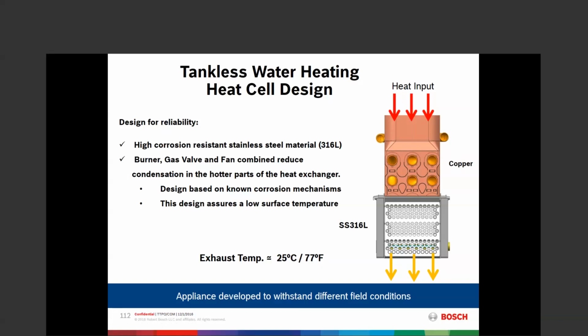And a lot of times some people are looking at that and going, hey, small tubes, that means high pressure drop, but it doesn't. And why it doesn't is these 50 tubes, the aggregate or total cross-sectional area of these 50 tubes has more than 4 times the cross-sectional area of a single pass of the copper tubes. So what actually happens is the water moves through this section, its velocity goes way down. Flow rate, gallons per minute, is going to stay the same, but the velocity goes way down. So in doing that, what we're creating is a huge wetted surface area. So there's a lot of surface area in contact with the water and a lot of surface area in contact with the flue gases. So we're able to achieve that very high energy transfer through the condensing heat exchanger.